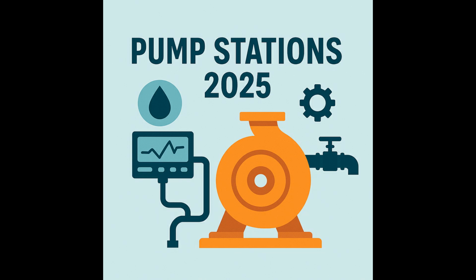And what does that comparison tell them? What's the purpose? Its main purpose is to confirm that the pumps are actually delivering their expected capacity under real operating conditions. It's often repeated periodically, maybe annually or even more frequently, for critical stations to check for things like wear, potential clogging, or just general reduced efficiency over time. So what if a pump underperforms on this test? That's a clear signal. If a pump underperforms on a drawdown test, it's a strong indicator that it might be operating outside its POR. It could be suffering from cavitation damage or experiencing other mechanical issues like impeller wear or bearing problems. This kind of rigorous testing is just crucial. It's the practical, real-world validation that ensures what was designed and programmed is actually delivering the expected efficiency and reliability. It helps catch potential issues before they snowball into critical failures.